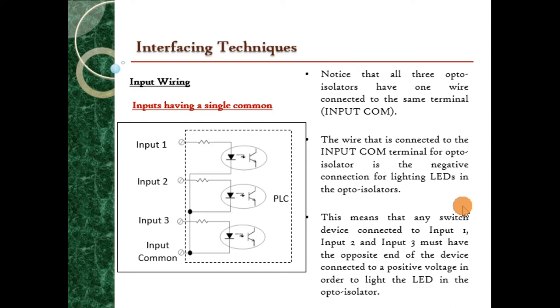If you can see here, this is the positive. The positive is connected to the input, and the negative of this LED is connected to the input common, so everything is connected to the ground here. This means that any switch device connected to inputs 1, 2 and 3 must have the opposite end of the device connected to the positive voltage in order to light the LED in the opto-isolator. So this input has some connection to the positive.